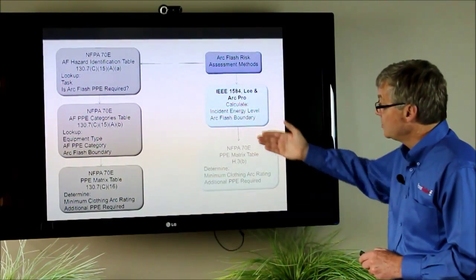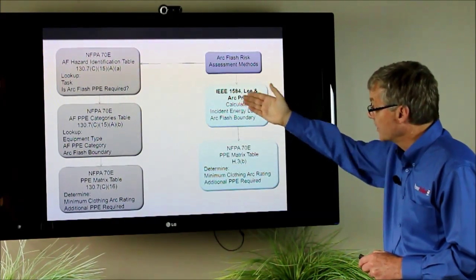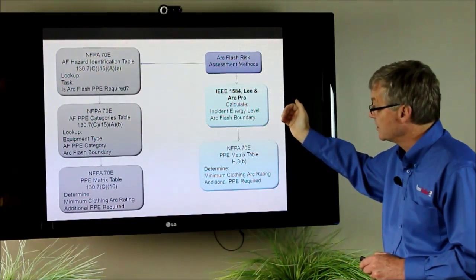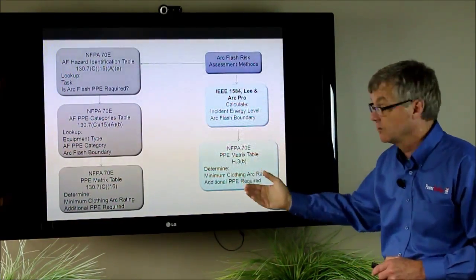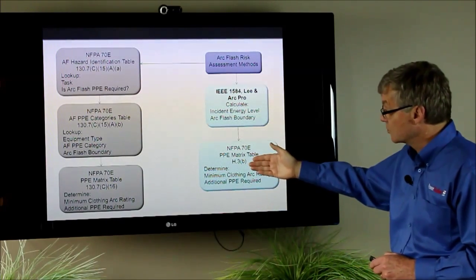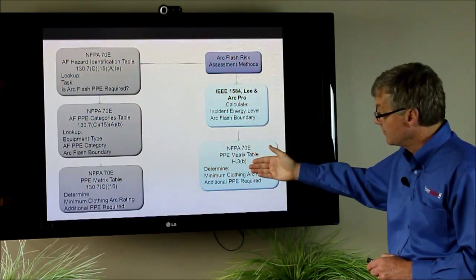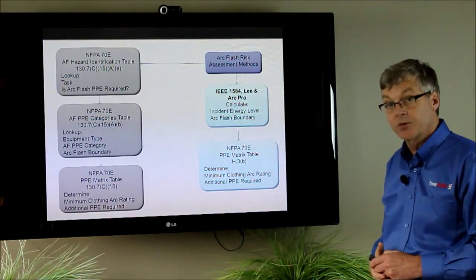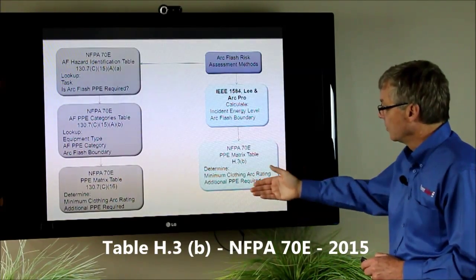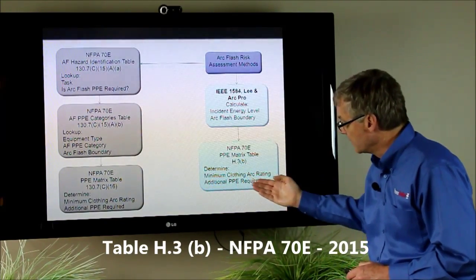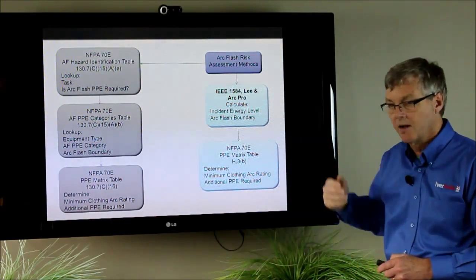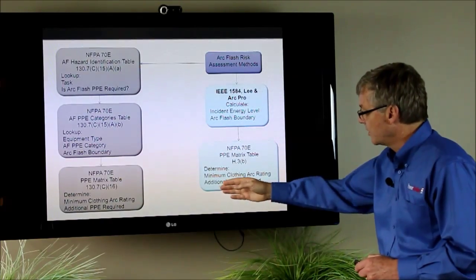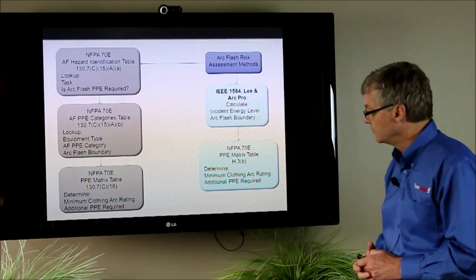And once you have determined using one of these three methods, the incident energy and the arc flash boundary, then you go to a different PPE matrix table in 70E. This one's in the back in the annex section and you go to table H.3B. There you'll look up what your minimum clothing rating is going to be based on the value you've calculated. There's three different levels and then also it'll tell you what additional PPE you have to wear.